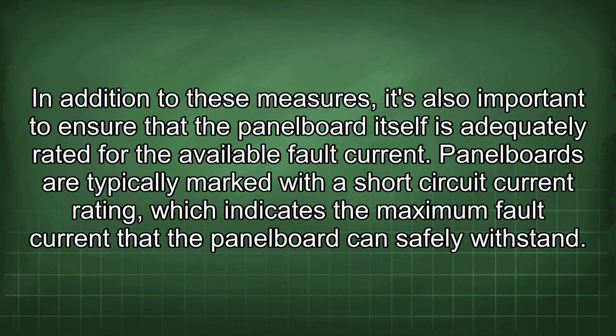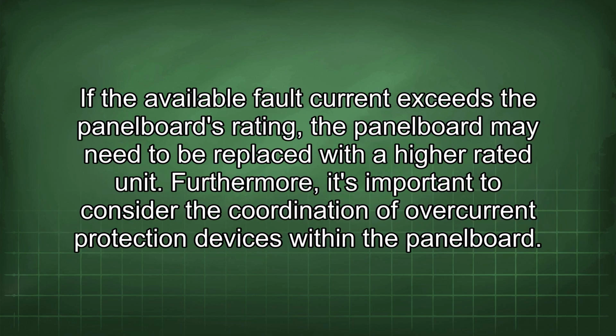In addition to these measures, it's also important to ensure that the panel board itself is adequately rated for the available fault current. Panel boards are typically marked with a short circuit current rating, which indicates the maximum fault current that the panel board can safely withstand. If the available fault current exceeds the panel board's rating, the panel board may need to be replaced with a higher rated unit.